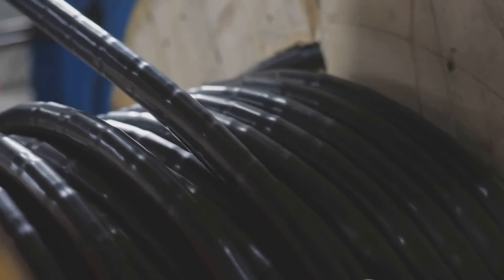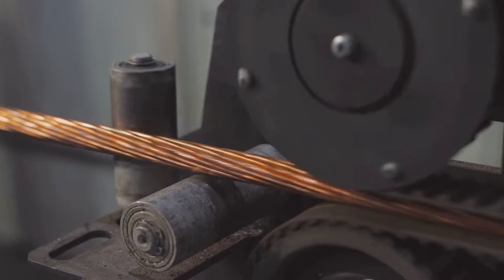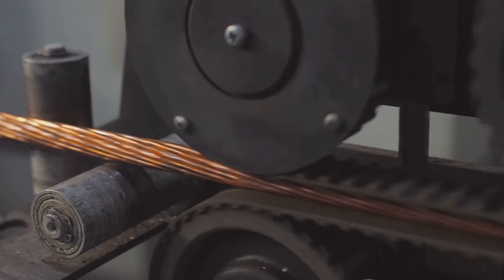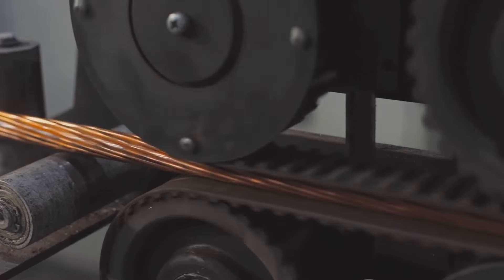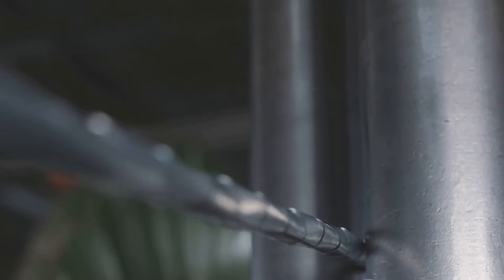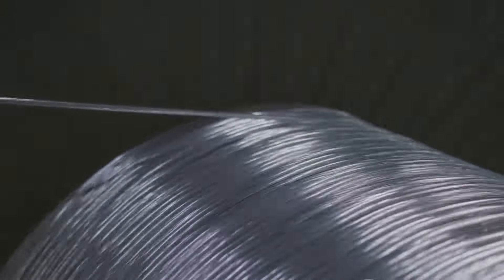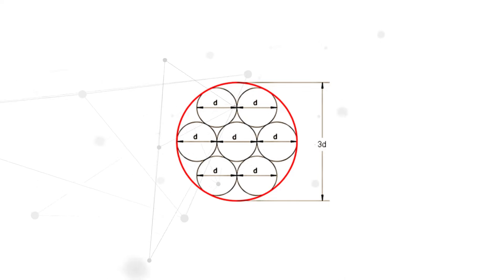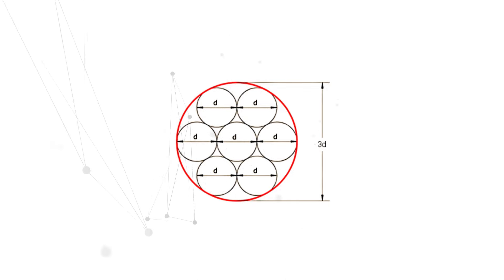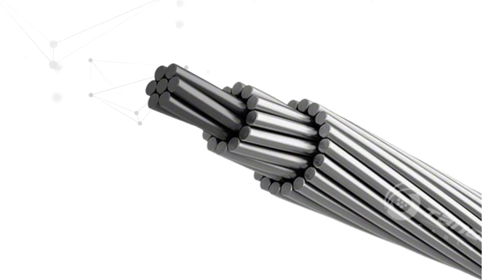There are several key facts to note about stranded conductors. Firstly, the stranded conductor has sufficient flexibility, making it suitable to be easily coiled for transport over long distances. Secondly, for a stranded conductor of the same cross-sectional area, the flexibility of the conductor increases with the increase in the number of strands. Stranded wires tend to be a better conductor than solid wire because the individual wires collectively comprise a greater surface area. The stranded conductor is formed by twisting the strands together in layers, with the strands of each layer laid in a helical fashion over the preceding layer — a process known as stranding.